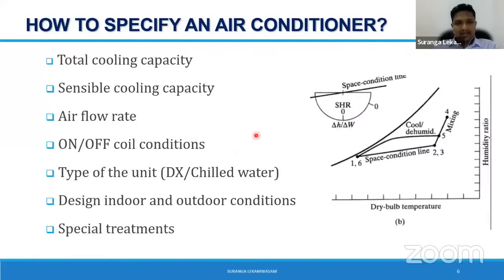Right. Now let's have a look. How do we specify your air conditioner? I mostly refer to the commercial level, not the domestic level. You have to specify certain parameters if you want to purchase an air conditioner. You have to specify the cooling load, the total cooling capacity. Then the sensible and latent cooling capacity. You know, there are two heat components which you need to remove with your air conditioner. Then the airflow rate, of course, you can calculate if you know the room sensible heat with the simple m c delta T equation. Then the cooling coil air condition.